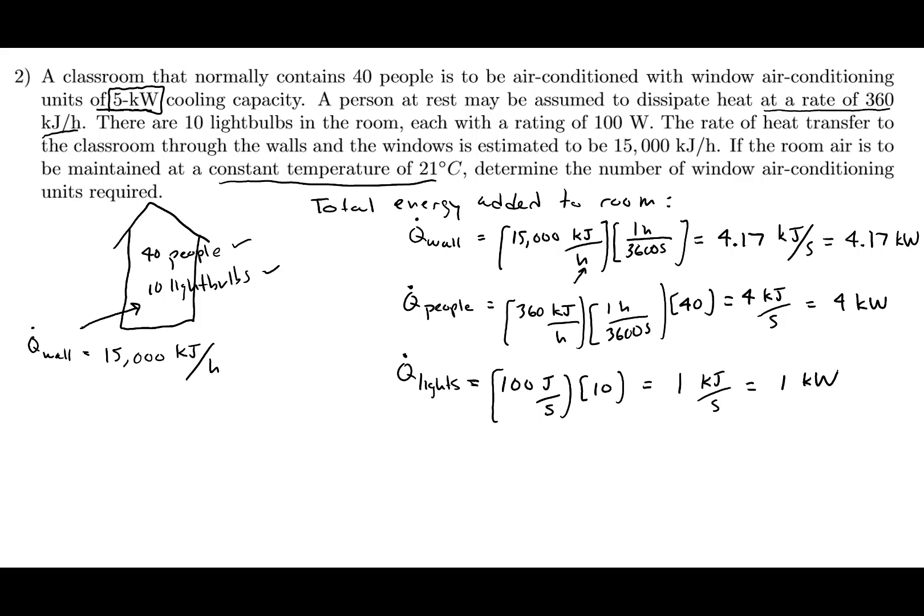Now what I can do is add up all of the heat that's added to the room, because that's the heat that the air conditioner needs to remove. Heat the air conditioner needs to remove is equal to Q wall plus Q people plus Q lights. This works out to 9.17 kilowatts.